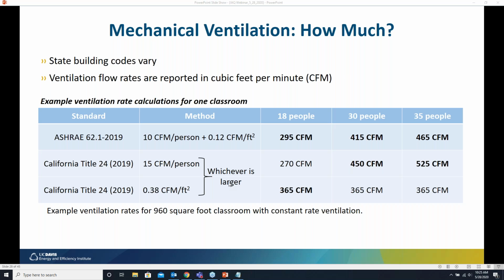So when we talk about mechanical ventilation, the question is, how much do we need? So I wanted to cover here building code requirements not related to COVID-19. But we can see here, state building codes vary. A lot of state building codes are based on a standard called ASHRAE 62.1. Ventilation rates are reported in cubic feet per minute. So I've done some example calculations for you here for one classroom, assuming that that classroom is 960 square feet. And at the top of the chart, we can see an increasing number of people requires an increasing amount of ventilation for that classroom. So for example, ASHRAE would say for a classroom with 18 people, you would need 295 CFM. And for 35 people, you would need 465 CFM.